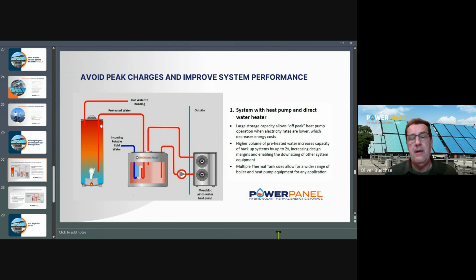If a building owner wants to have that water boiler in place as a backup, they can now design it and reduce the scale. So not only can you save on ongoing operating expenses, but you can also scale back your system requirements and put in a smaller water heater because you have that preheating and thermal storage capacity.